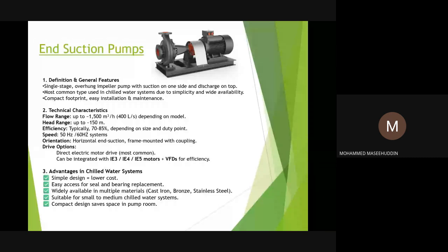Now, the typical specification for our chill water pumps in this segment is that we use mostly cast iron casing, bronze impeller, and stainless steel shaft. Most of the pumps are specified this way. But obviously, when there is a requirement, for example, the water quality itself is very aggressive or something, we can also prefer stainless steel 304, 316, 316L, or even duplex pumps. So we do have various material options for these pumps as well, which are suitable for small to medium chill water systems.